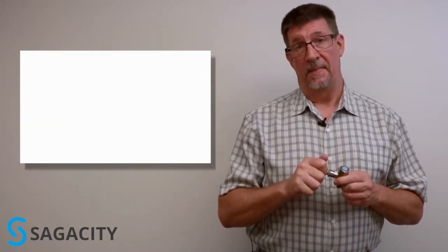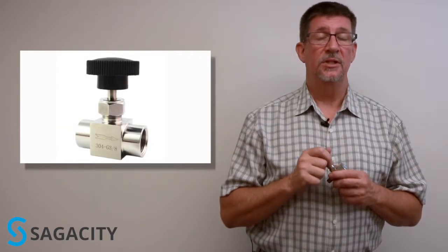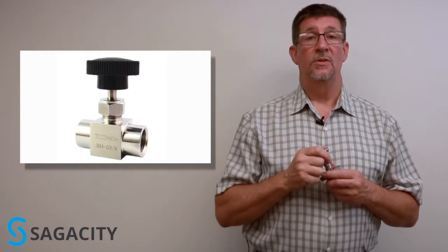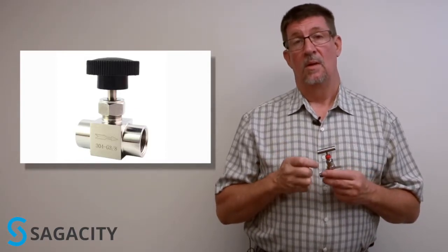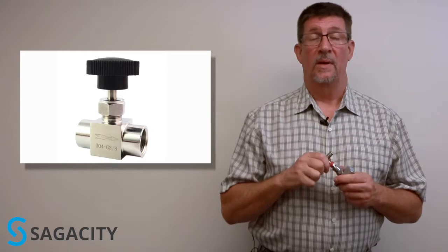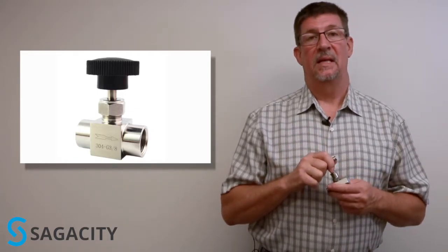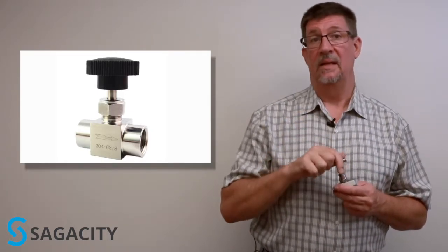However, if you see a knob type handle, that usually indicates a precision type needle valve that is being used to control flow, say, into a rotometer or other analyzer, or any type of device that needs to have flow controlled precisely in that application.